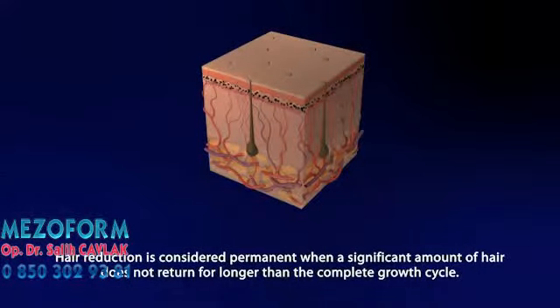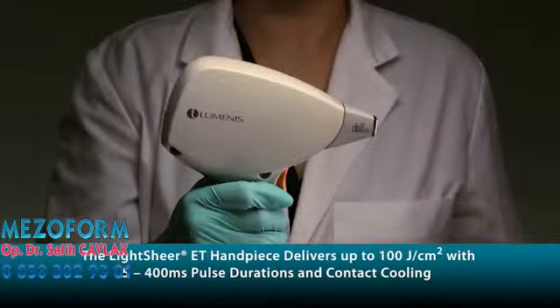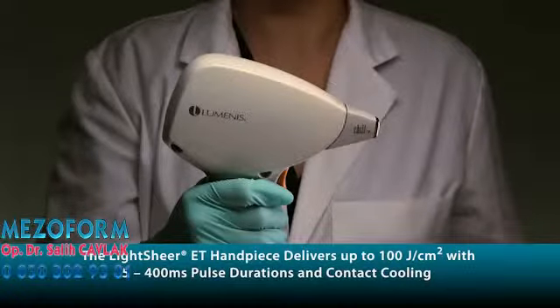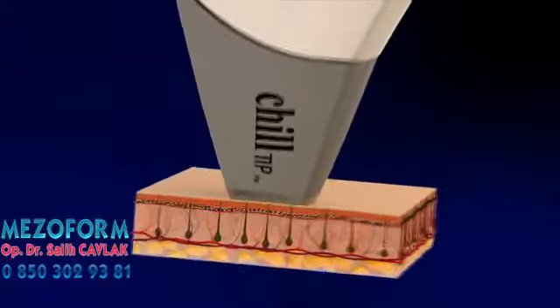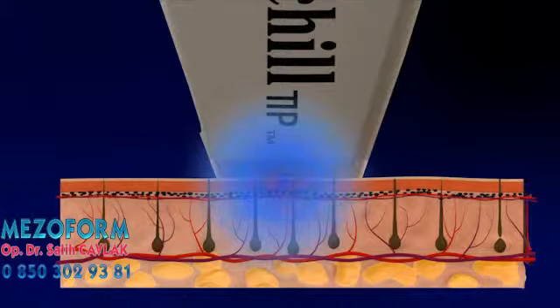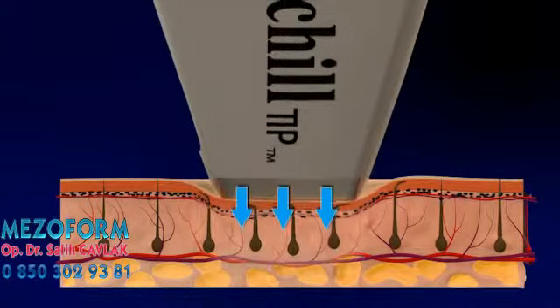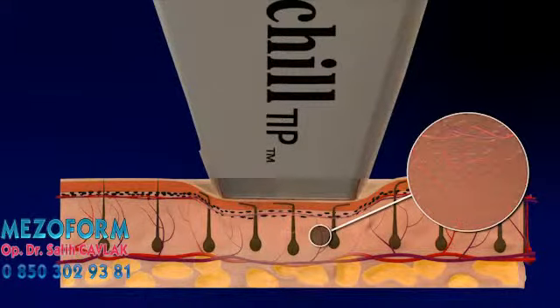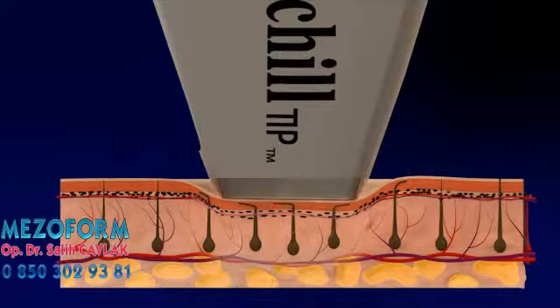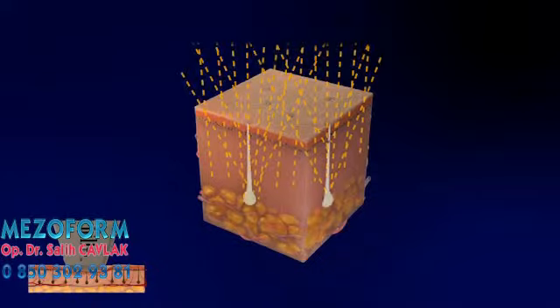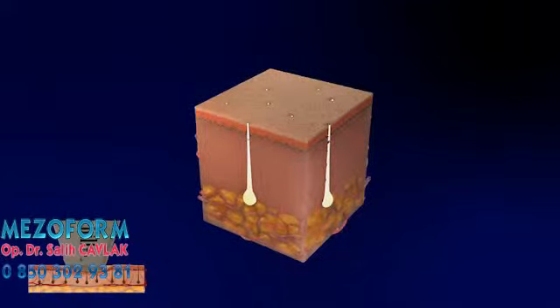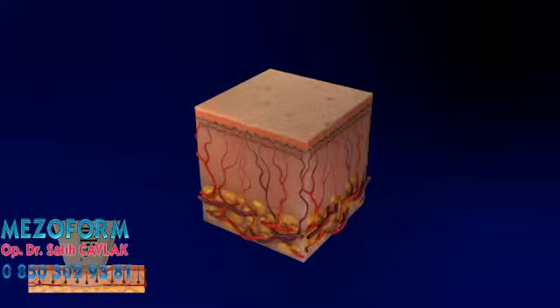Hair reduction is considered permanent when a significant amount of the treated hair does not return for longer than the complete growth cycle. The ET handpiece delivers up to 100 joules per centimeter squared with 5 to 400 millisecond pulse durations and contact cooling. Contact cooling with the chill tip cools the epidermis before, during, and after each laser pulse. The chill tip sapphire window, in direct contact with the skin, also reduces internal reflection of backscatter light. Compression of the skin with the chill tip temporarily displaces oxyhemoglobin, a chromophore that competes with melanin, and flattens the epidermis, which brings the hair roots closer to the surface. Combined, these effects protect the epidermis and enable more light to be absorbed by the hair follicle and root. Melanin in the hair follicle and root is heated to the point of thermal damage, which reduces the ability to regrow.